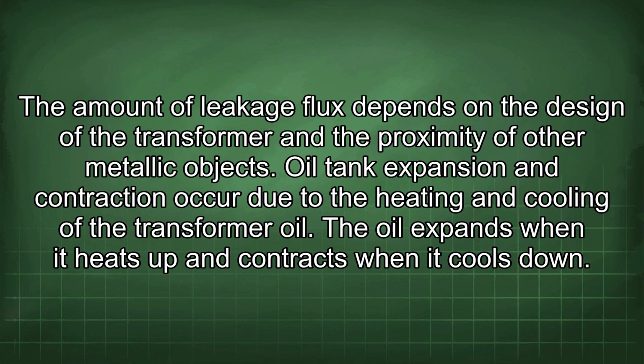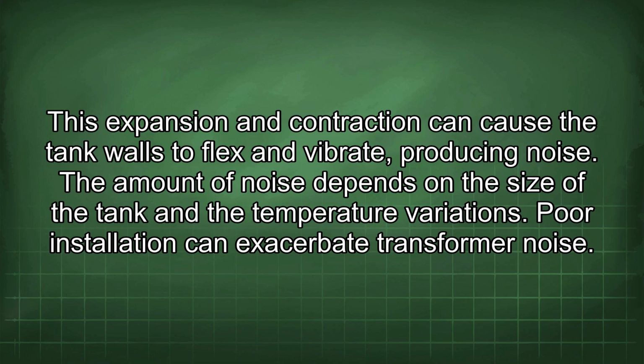Oil tank expansion and contraction occur due to the heating and cooling of the transformer oil. The oil expands when it heats up and contracts when it cools down. This expansion and contraction can cause the tank walls to flex and vibrate, producing noise. The amount of noise depends on the size of the tank and the temperature variations.